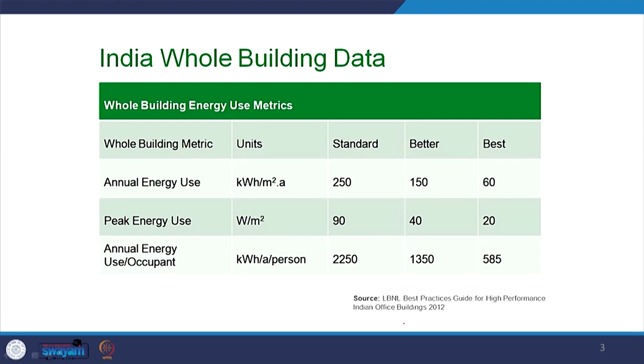If we look at the current data for energy consumption in buildings published by LBNL in 2012, the standard annual energy use — the EPI — for Indian air-conditioned buildings is around 250 kilowatt-hour per meter square per annum, and the best is around 60. On an average, many buildings in India do not use air conditioning and have an annual EPI of around 100.